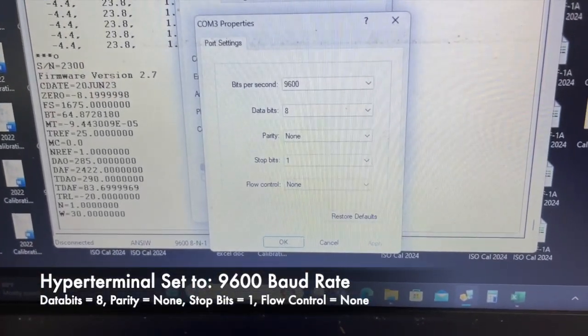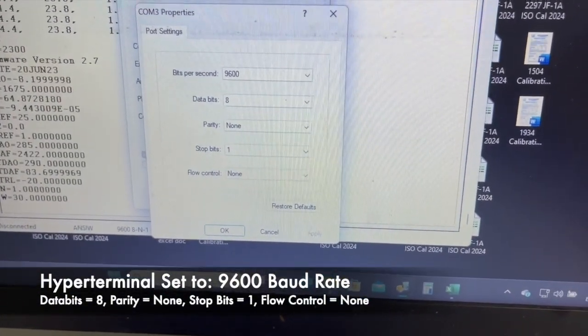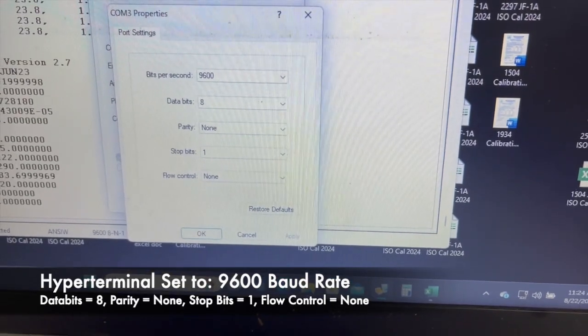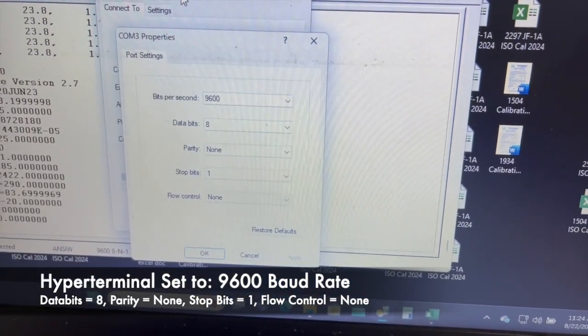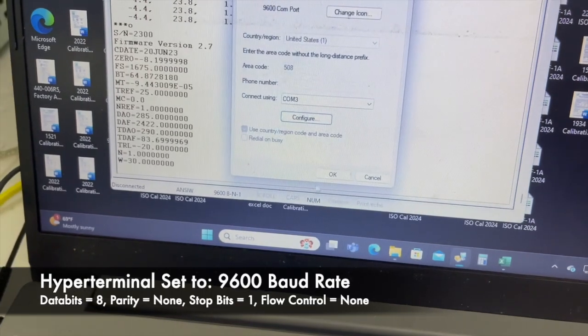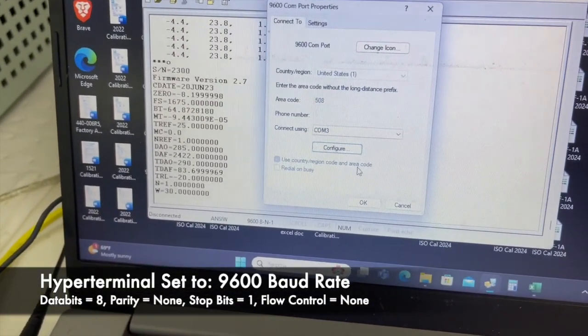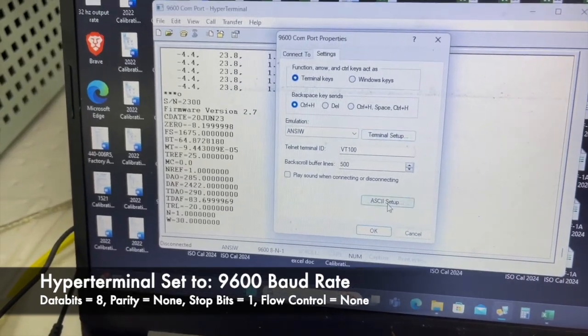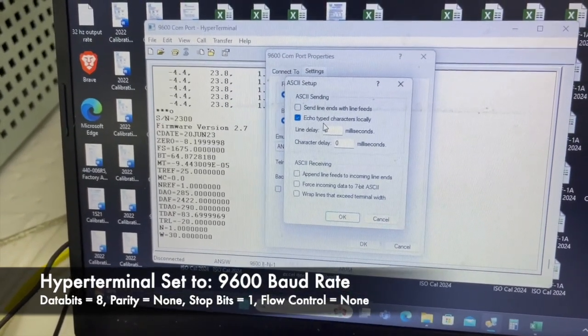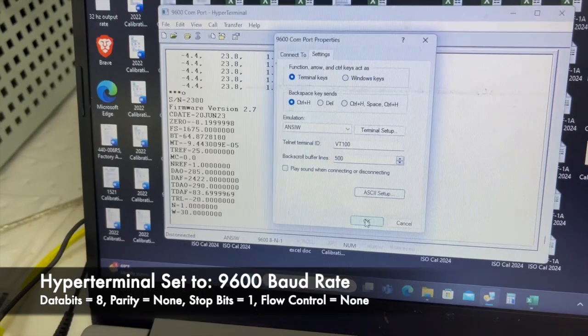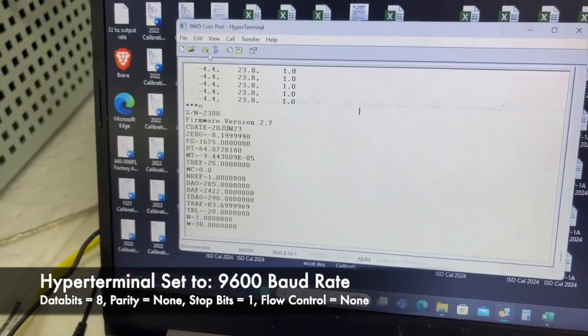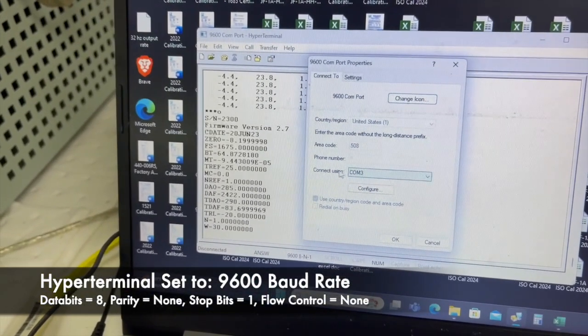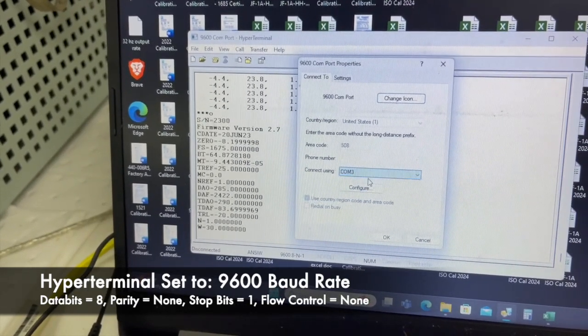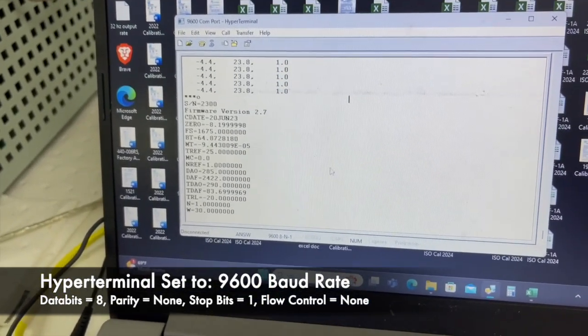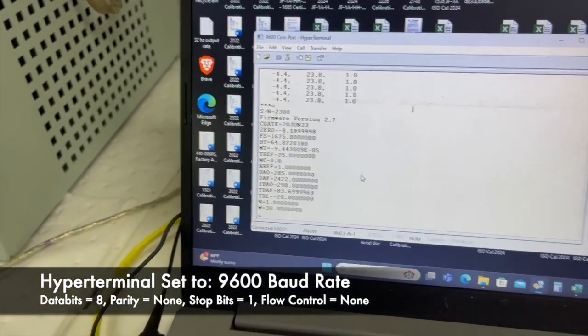And you want to open up a new connection, set it to the following: bits per second 9600, data bits 8, parity none, stop bits 1, flow control none. Hit OK. You can configure further settings if you want, like these. I tend to put on echo typed characters locally just to make it easier. Okay. Then you go over here and you connect, you pick the correct COM port, which for me is COM port 3. And then you go over here and hit connect, and it should be open.